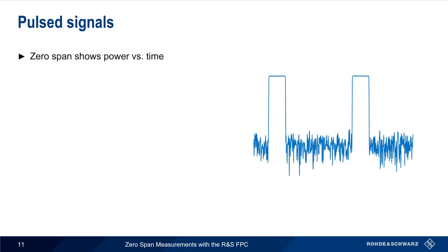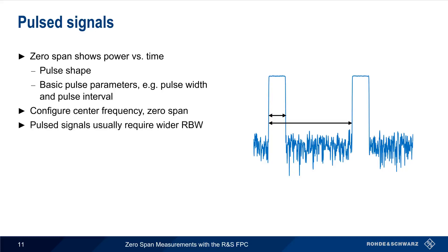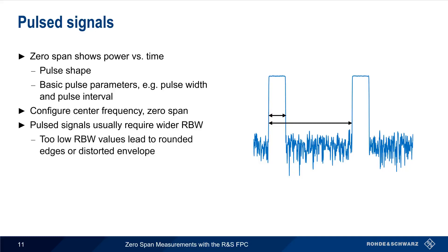The last zero-span application we're going to look at involves pulse signals. Specifically, we'll be using zero-span to view the pulse power versus time envelope, so we can examine both the pulse shape as well as determine basic pulse parameters such as pulse width and pulse interval. As always, we'll need to configure center frequency and set the span equal to zero. Because pulse signals tend to have wide spectral content, we'll most likely need a wider resolution bandwidth setting. Too small of a resolution bandwidth can lead to rounded edges or distorted pulse envelopes. And lastly, we'll also need to configure a trigger to freeze the pulse signal on our display.